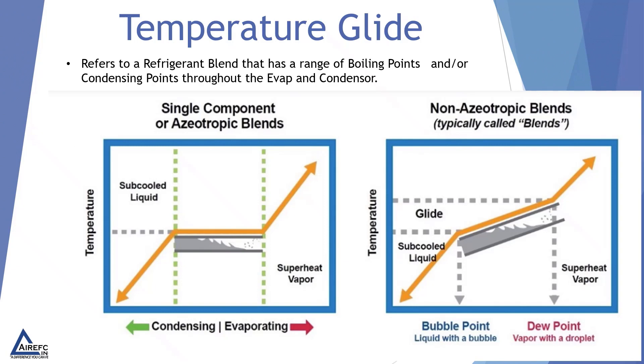Temperature glide refers to a refrigerant blend that has a range of boiling points and/or condensing points throughout the evaporator and condenser. The diagram on the left shows single component or azeotrope refrigerants, which have the same temperature between their subcooled liquid and superheated vapor states. On the right, non-azeotrope blends show a glide — a range of temperature between the subcooled liquid and the superheated vapor where the refrigerant is either boiling off or condensing back into a liquid.